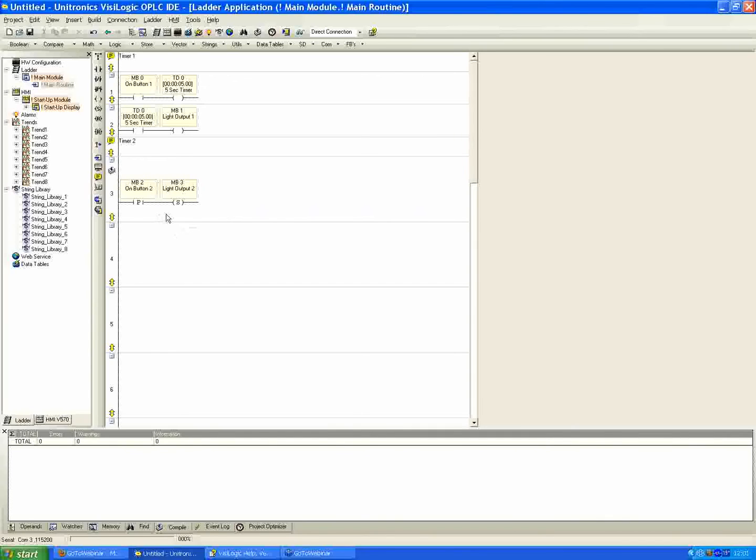So if you pulse the set coil here, it's going to hold its state. It's going to stay set until there is actually a reset coil somewhere in the program to have that go back to its low state. So it's a set and a hold, basically. There's no latching circuit required. It's built in with these type of set and reset coils.